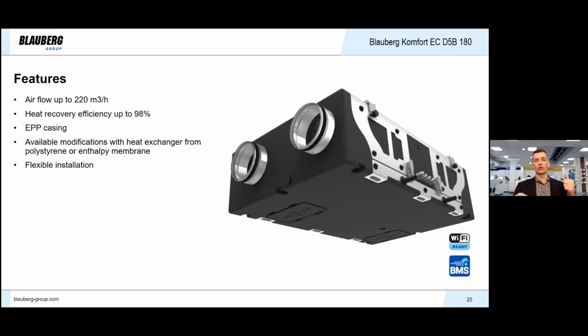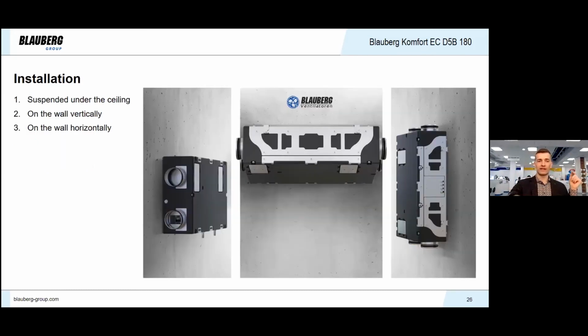It makes it very light. Only one installer can install it, for example, suspending the unit under the ceiling. In total, the unit weighs about 18-20 kilograms. You can take a look and get the exact number in our catalog. And flexible installation: on the next slide, I would like to highlight this particular feature. You can install it in almost any position you imagine. First of all, the most popular one is to suspend it under the ceiling. Then you can install it vertically on the wall or horizontally on the wall. This is a very nice feature for installers and consultants also.